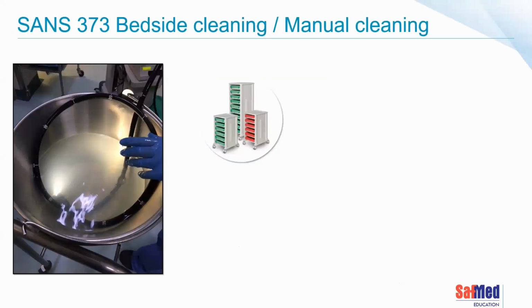In SANS 373, there is reference to pre-cleaning at the bedside, or a bedside cleaning process, as in all of the other international standards. Hopefully we're not using these horrid metal buckets to do that with. That bedside pre-cleaning process does include wiping down the insertion tube, sucking through the detergent water mix, and blowing out air. But of course, all of this still needs to be in line with what the manufacturer's instructions say.